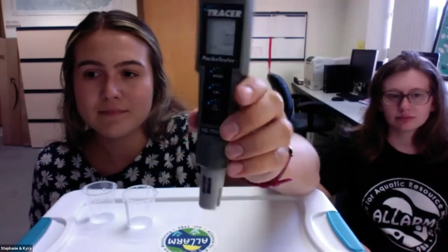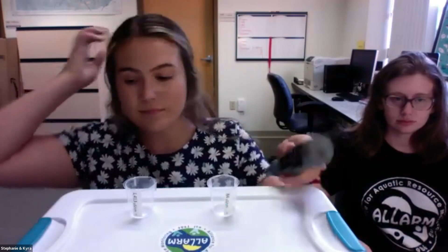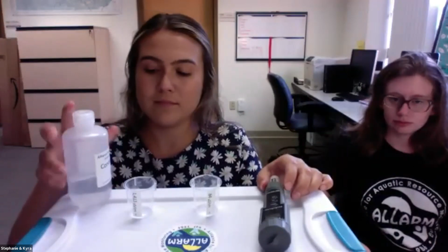Nice, good job. All right, so we're in conductivity mode. And then the next thing that we are going to do is start the calibration process. We're now at the bottom of page 6 in step 2, calibrate the meter with 84 microsiemens per centimeter calibration solution.